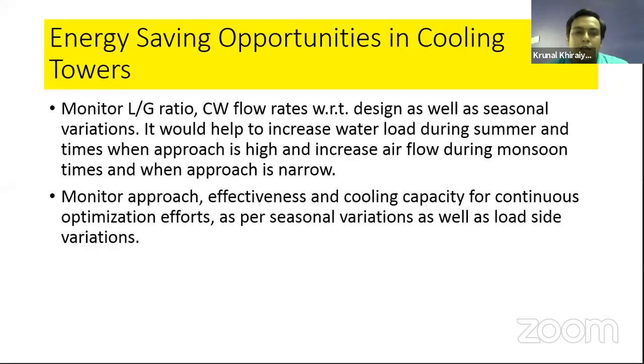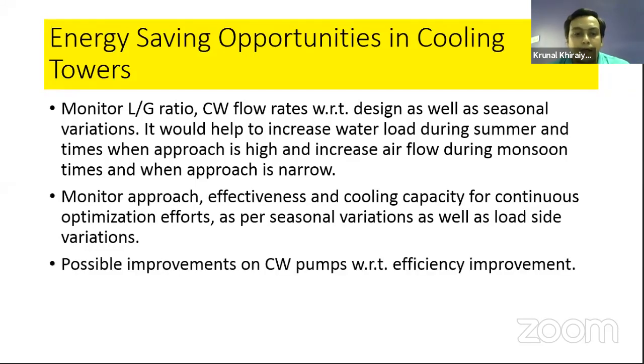Every time, you need to take a reading of the cooling water in, cooling water out, as well as the ambient air temperature, and on that basis you need to monitor the approach and effectiveness, so that you can have a clear, continuous idea whether your cooling tower is running with the given load conditions or not.